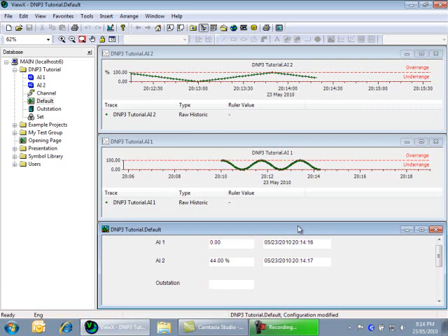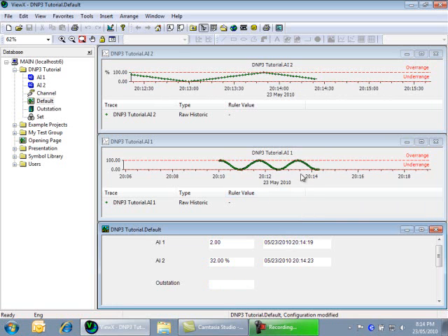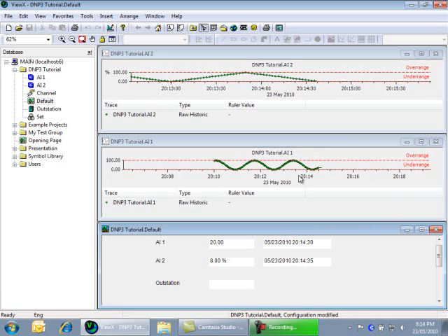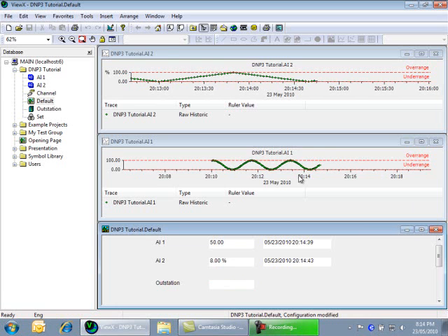You will see that because the data is being stored in the RTU, we haven't lost data. Everything that occurred is transferred to Clear SCADA when the comms is re-established. The history is maintained, and the user has a record of the comms failure in the event journal for future analysis. This is one of the key benefits of DNP3 in that a comms failure does not mean a loss of critical process data, billing information, or data mandated for regulatory compliance.